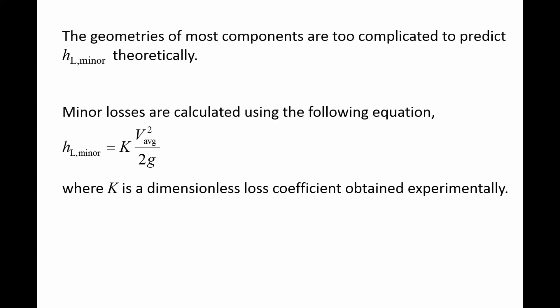For each component, the minor loss is equal to K times V_average squared over 2g. K is a dimensionless loss coefficient that is obtained experimentally. Higher K values indicate higher losses for the same flow speed.